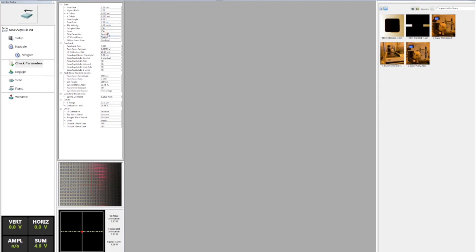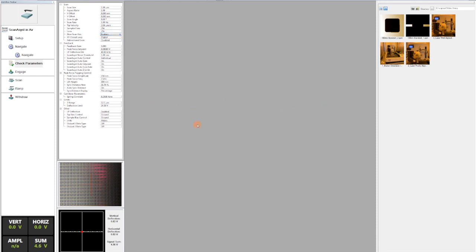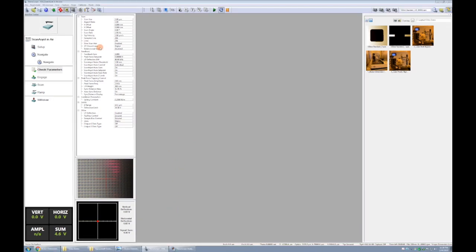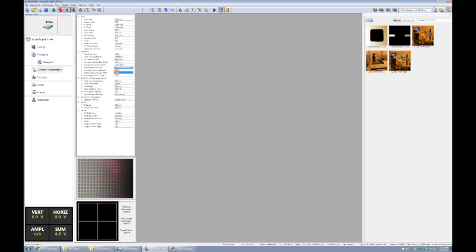We'll put those back to where they were. The slow scan axis just means are we enabling a 2D scan? The y axis is the slow scan axis. If it's enabled, you'll get a 2D image. If it's disabled, then you'll scan the same line over and over, and what gets displayed along the y axis will be the time dimension. We'll skip these two and move on to feedback.